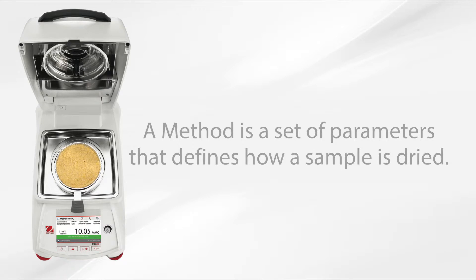A method is a set of parameters that defines how a sample is dried. A method consists of a drying program, drying temperature, shutoff criterion, display mode, target weight, and start mode.